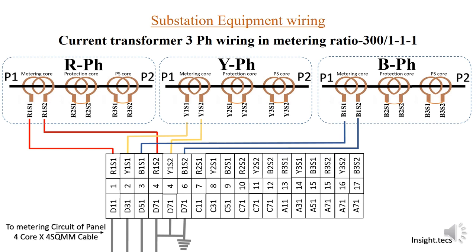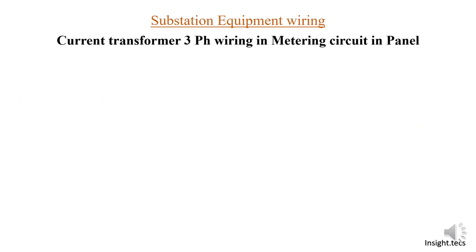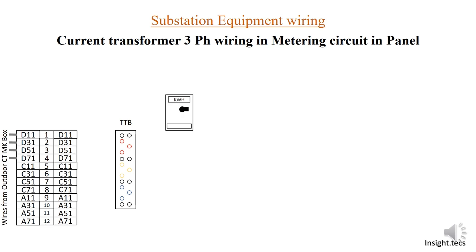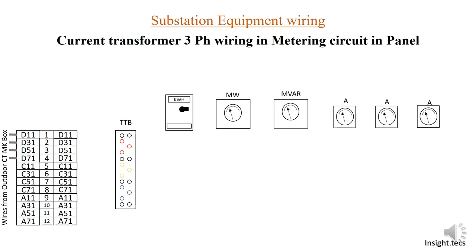In this video we are going to learn how these four wires are used inside the panel in the control room. The four wires coming from the current transformer in the yard enter the panel. The very first element in the wiring is the TTB, that is the test terminal block. Then there is the kWh meter, which is the energy meter, followed by the megawatt meter, the MVAR meter, and the ampere meter to measure current.